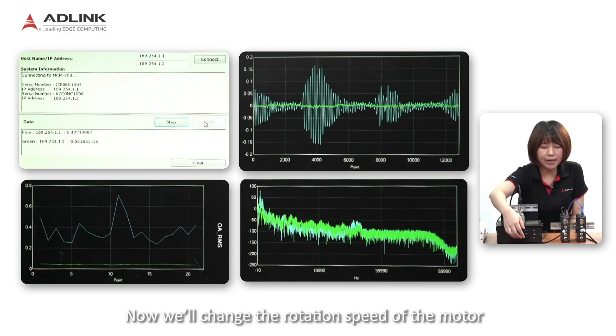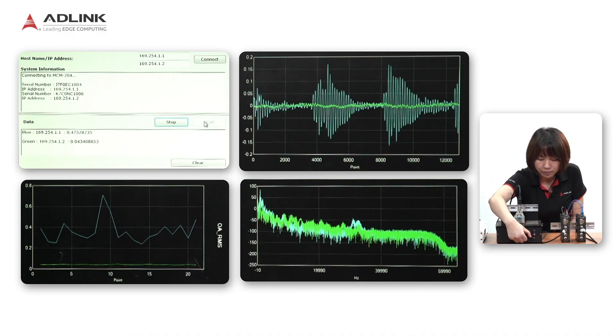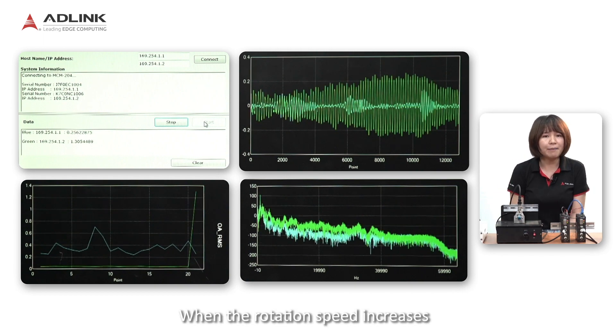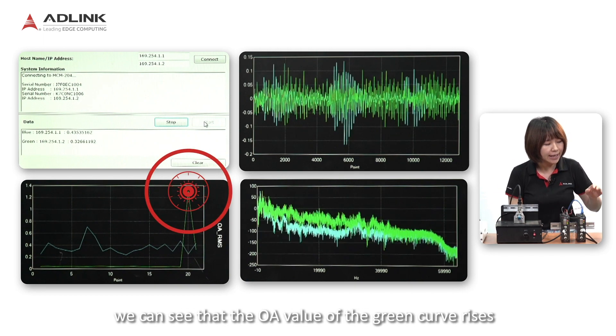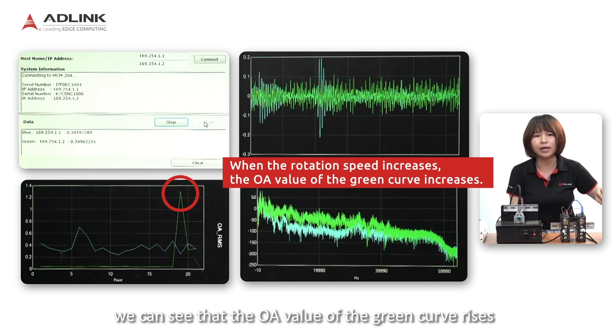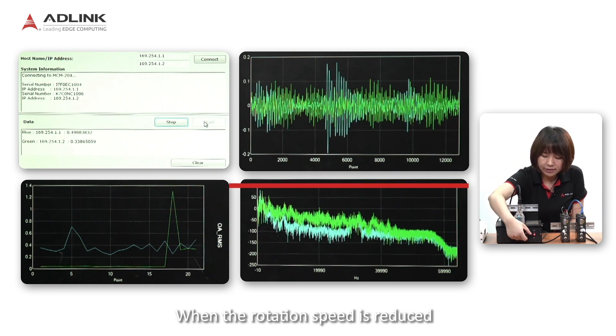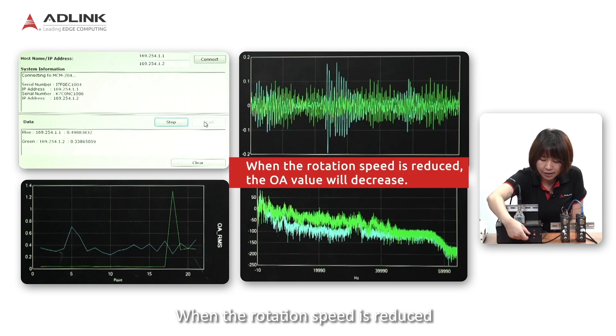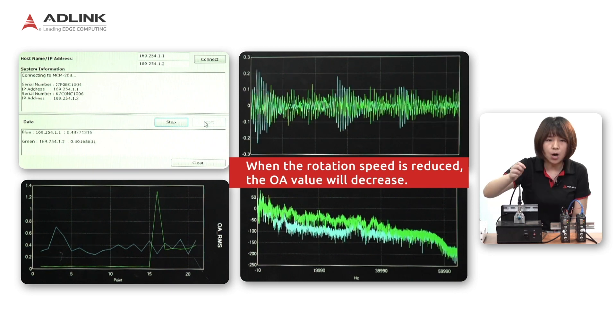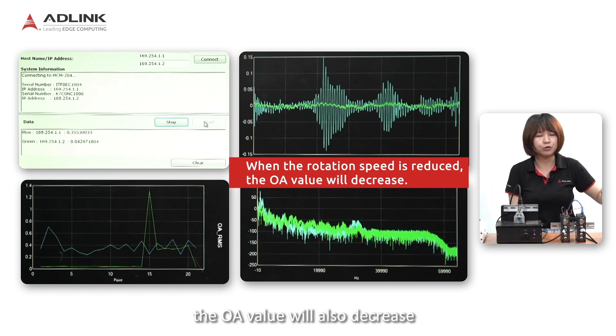Now we'll change the rotation speed of the motor. When the rotation speed increases, we can see that the OA value of the green curve rises. When the rotation speed is reduced, the OA value will also decrease.